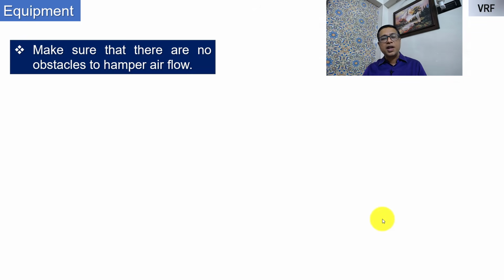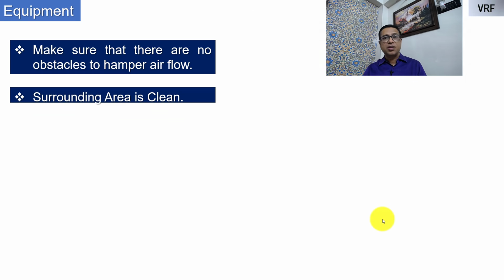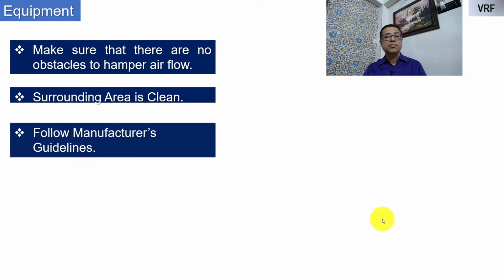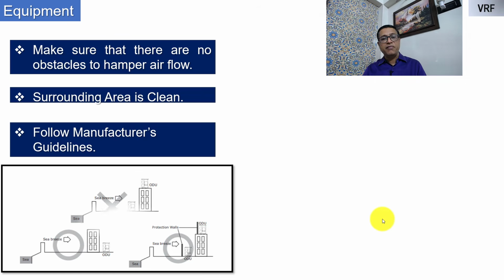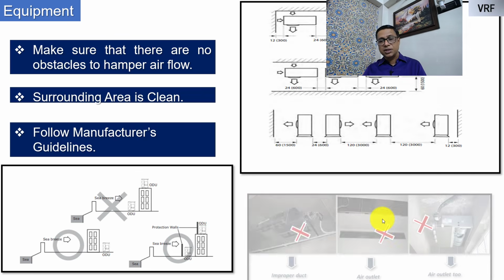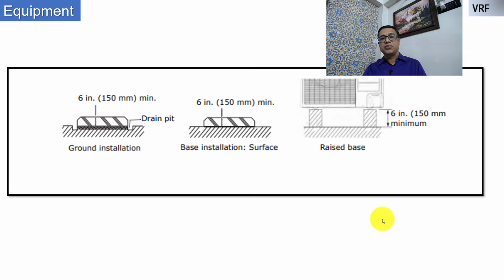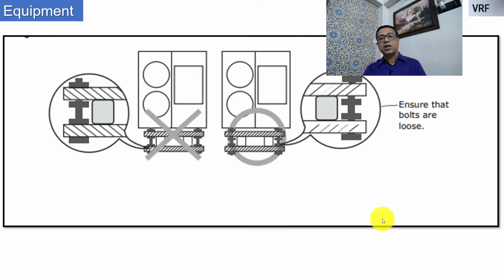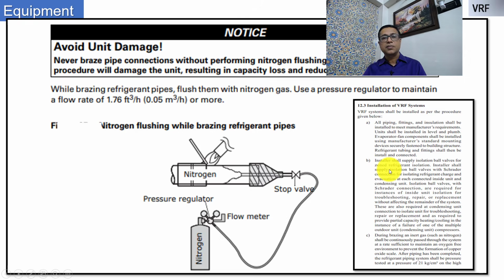So make sure there are no obstacles for airflow when we talk about VRF outdoor units. The surrounding area needs to be clean, and we need to follow the manufacturer guidelines for doing the VRF installations. This is how the base of the unit can be installed. This is not the way to install. If you have a vibration isolator, this is the way to install. You can see it here.